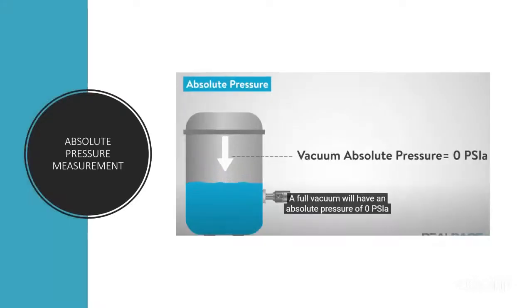And then regarding the absolute pressure, in this case, the sensor measures pressure against vacuum. Normally, a vacuum pressure is 0 psi. So if you desire to measure a value that is less than the atmospheric pressure, you use this kind of pressure sensor for absolute measurement. In practice, it normally tells how much vacuum or negative pressure exists in a system.